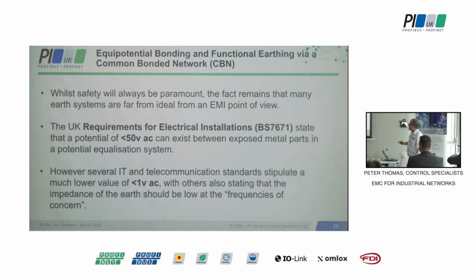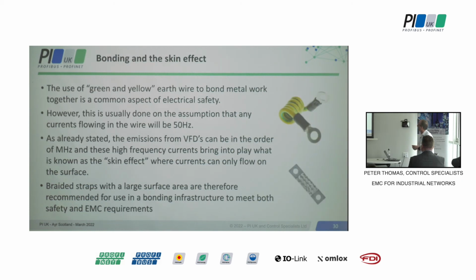Several IT and telecommunication standards say that it needs to be less than 1 volt, and others say it can be whatever it is, as long as it's that at the frequency of concern. And the frequency of concern is whatever frequency is causing you a problem. So in drives, for example, drives give off a few megahertz, so the frequency of concern for drives is maybe a few megahertz, and that's how we would go about improving things.